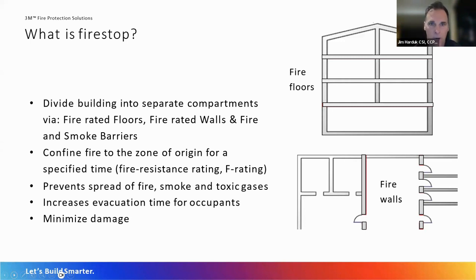But aside from the obvious fact of trying to contain a fire, these fire-rated floor and wall assemblies must also prevent the passage of flame, smoke, and toxic gas. Because if you remember, as I said before, most fatalities happen due to smoke inhalation and toxic gas. So for a fire-rated floor and a fire-rated wall assembly to operate properly in the event of a fire, it has to be continuous. But we have one problem here: during construction, we have to cut holes in our fire-rated floor and our fire-rated wall assemblies to run electrical cable, to run plumbing, to run HVAC ductwork. So anytime we disturb a fire-rated assembly, whether it's a floor or wall, we need a means and methods to restore it back to its original intended rating. Next slide, please.